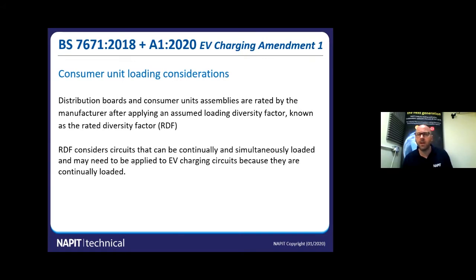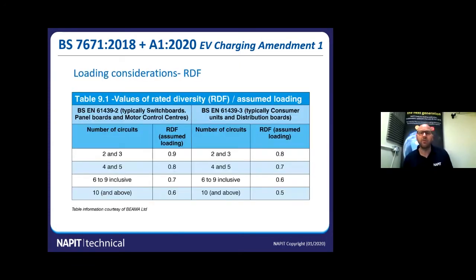And we need to apply this because EV chargers are a constant load. So unlike a shower or something that goes on, 5 minutes later it's off, there's no real concern. An EV charger could be on for quite some time. Okay, so we need to look at the RDF factors. Now, you've probably never noticed this, or you may have noticed this, but if you look in consumer unit instructions, quite often you'll see some little tables and charts. Next time you're doing a board change, have a look and see if you can find some advice on RDF. This table here is from the product standards and actually from BEAMA. If you look at the BEAMA documents, they've got all this stuff readily available.